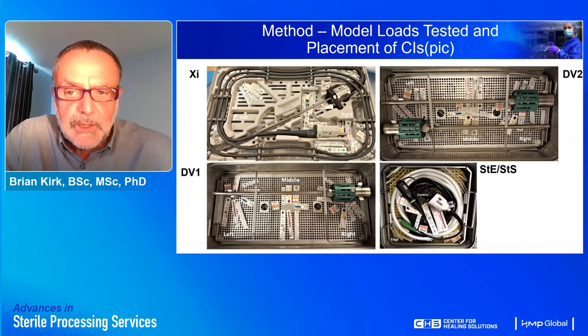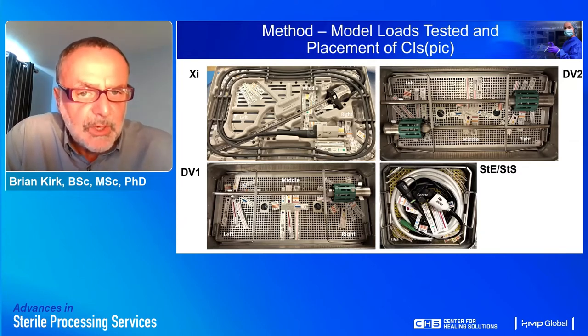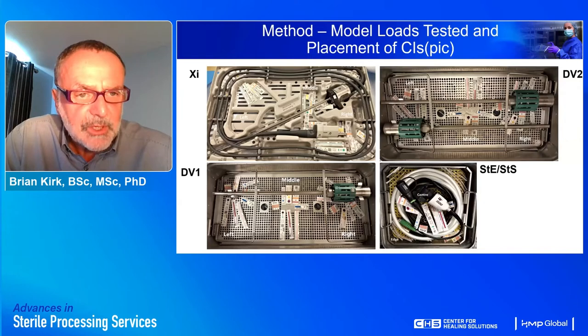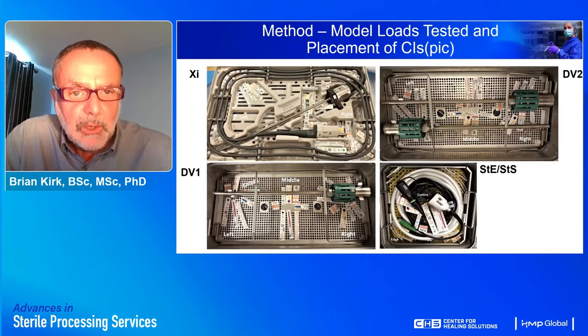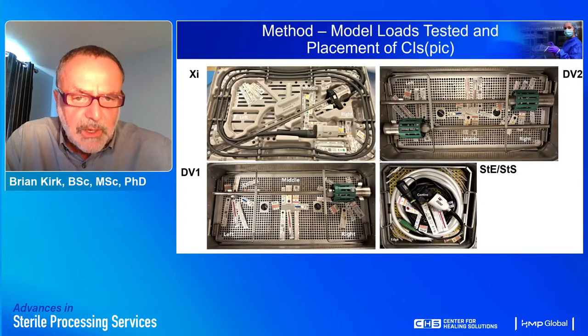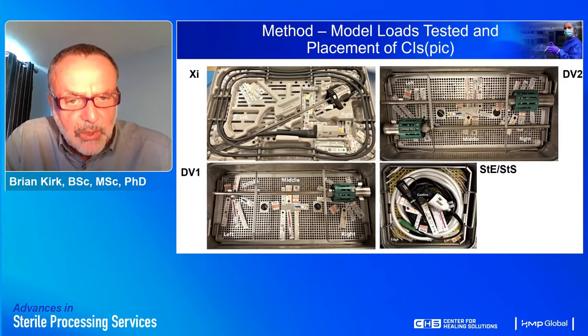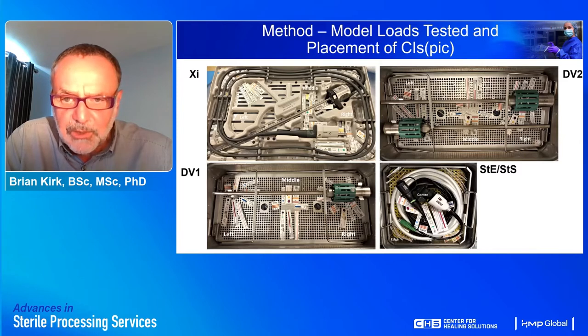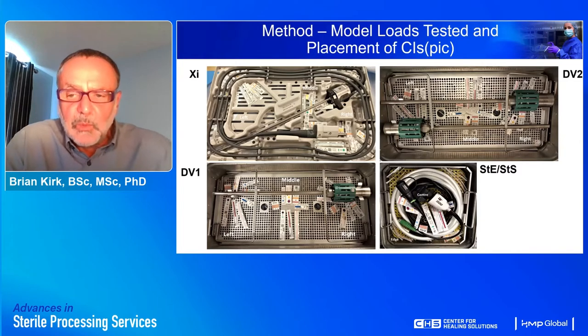For loads StE and StS, CIs were placed either at center or edge. The indicators were positioned in the left, middle, or right-hand side of the individual load items; for StE and StS they were either placed in the center of the model load or arranged around the outside, supported within the porcupine mat visible in the corners of the sterilization container.